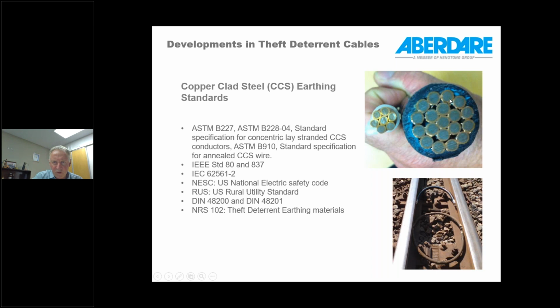There are some pictures of copper-clad steel conductors, and there are quite a number of standards that specify the requirements for these metals. So it's not, let's say, an uncontrolled industry. If you order this material from a reputable manufacturer and supplier, you will find that you're getting the proper quality of metal that you're expecting. So quite well standardized, particularly in the American environment.